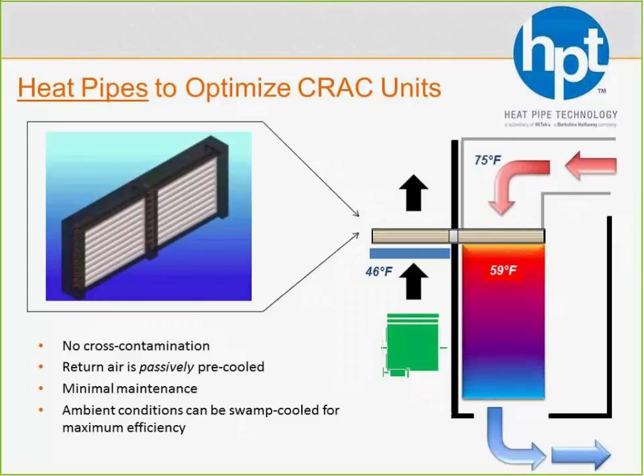And you can actually go one step further if you're in a drier environment especially. You can use evaporative cooling to spray some water on the outside portion of the heat pipe, and it fools the heat pipe, so to speak, into seeing cooler air conditions. So now instead of a 20-degree delta T, it might see a 30-degree delta T. And if that's the case, you're going to get about 50% more heat removed. So this is certainly location dependent.